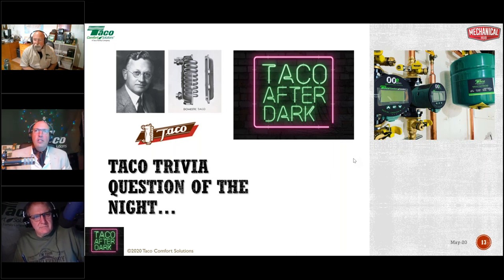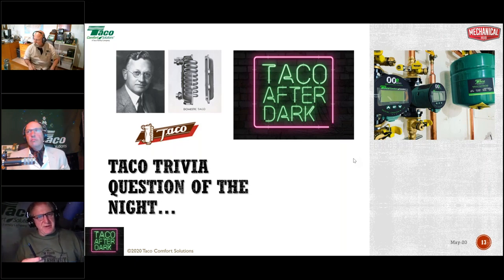But otherwise, oh yeah, definitely on a ModCon boiler. The colder the water, I want to send ice cubes back to that boiler. So yes, definitely. Also, if you're dealing with a two-pipe system or a direct return, like a typical European system, again, we don't install many of them here, where you've got a supply and a return back to a main manifold, each radiator has its own supply and own return. In that case, it's just one panel, right? You could do a 40 degree delta T there if you wanted to. You've got a big piece of aluminum filled with water to absorb that. So yeah, you could do it there as well.